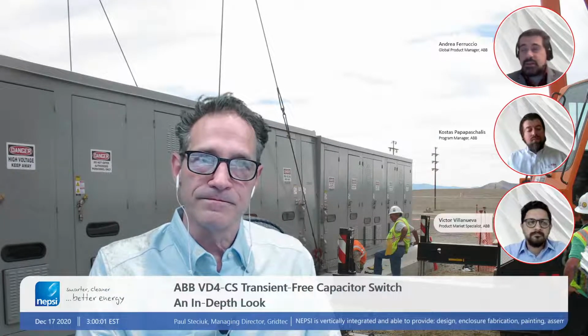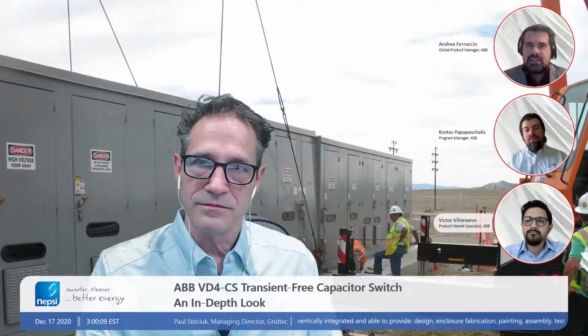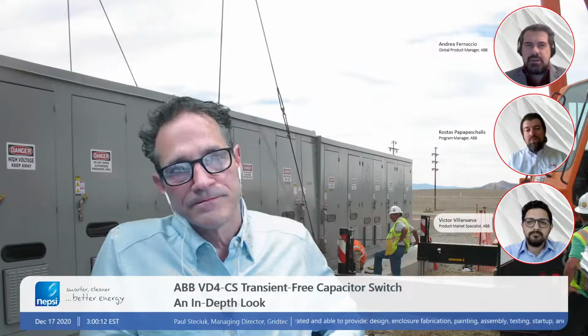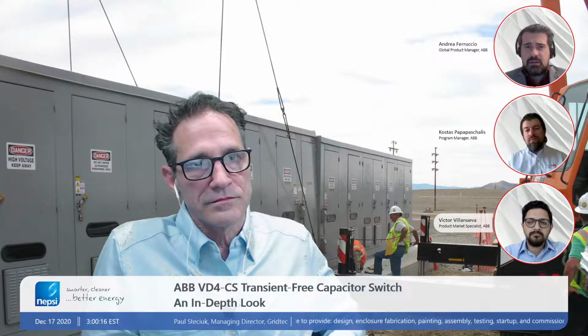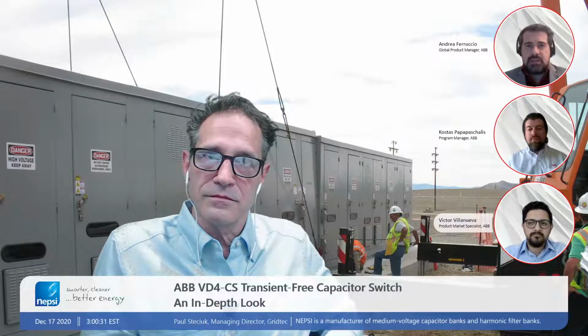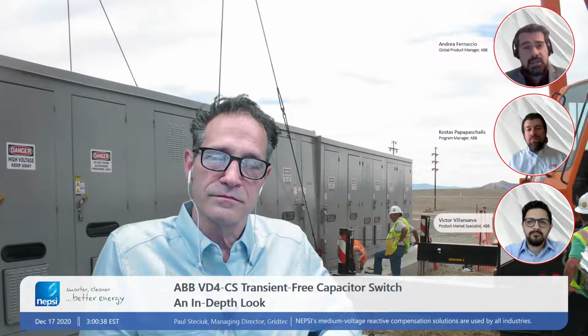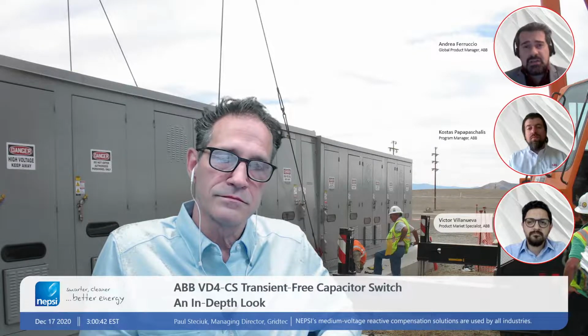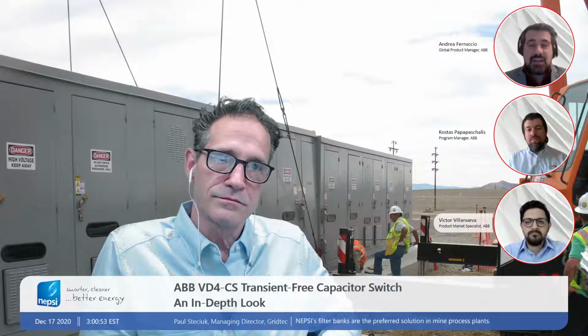Yeah, I can take it, Paul, and thanks again for this question — it's really technically interesting. We have to consider that everything in the VD4-CS is new and dedicated to a very specific application, which is switching capacitor banks in order to eliminate the transients we normally experience during opening and closing of such loads. To do that, as I explained, we have a new actuation system, with very precise control in the actuation and in the reading and measurement of the reference voltage and electrical parameters. We also have new, innovative vacuum interrupter technology. Going into more detail, unfortunately, isn't possible, as it would take a long time.